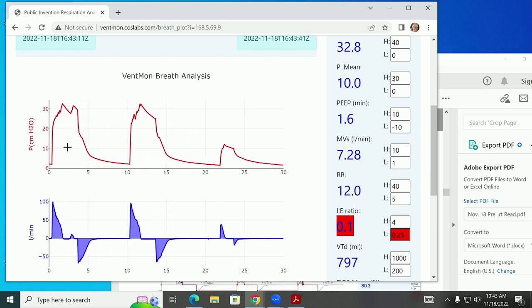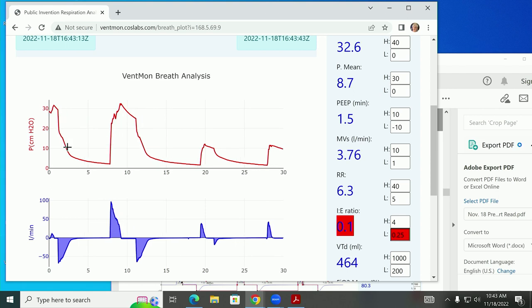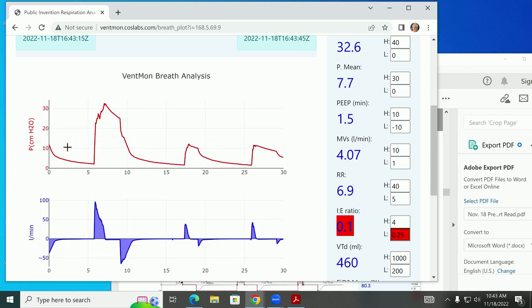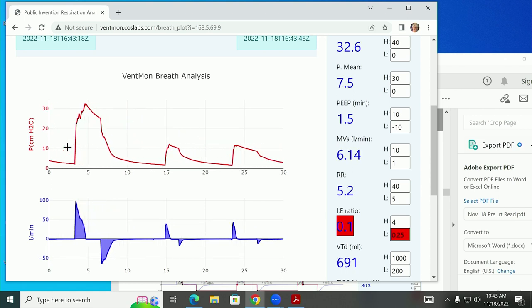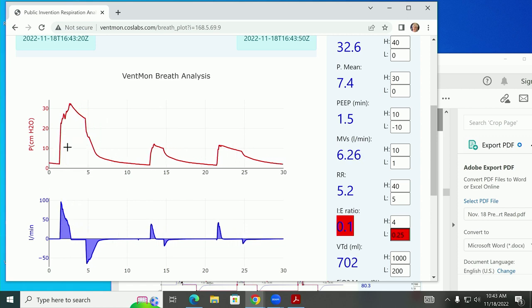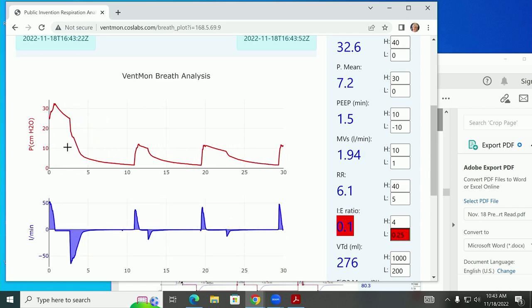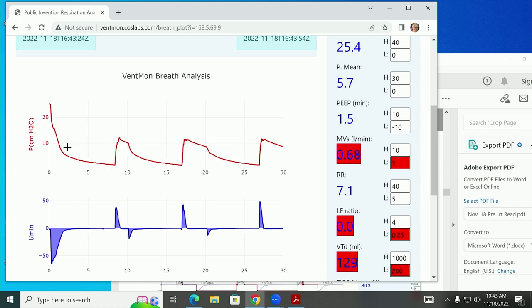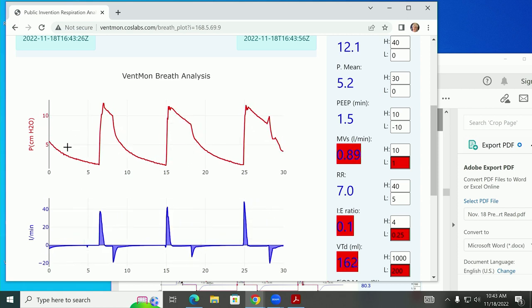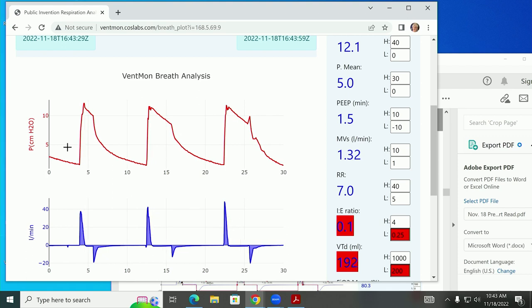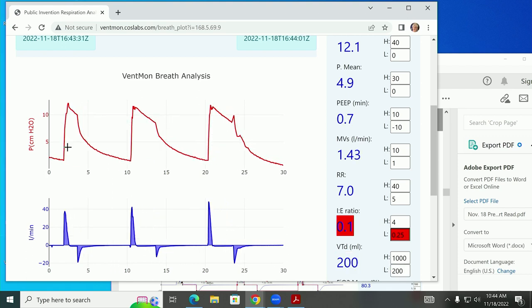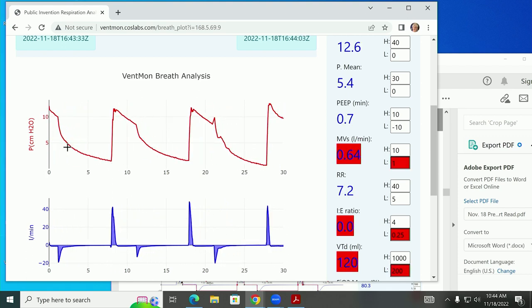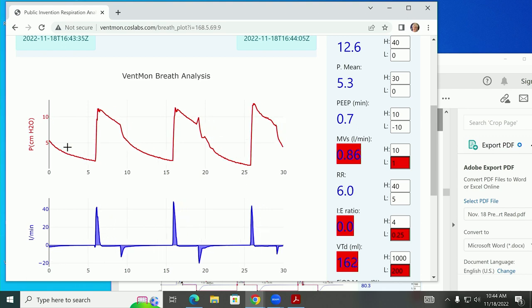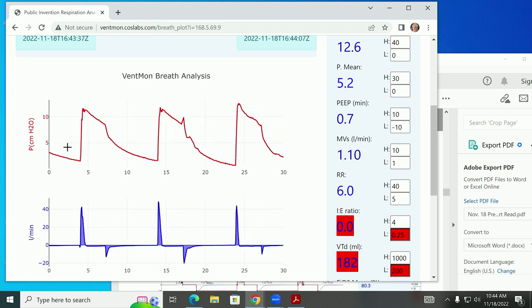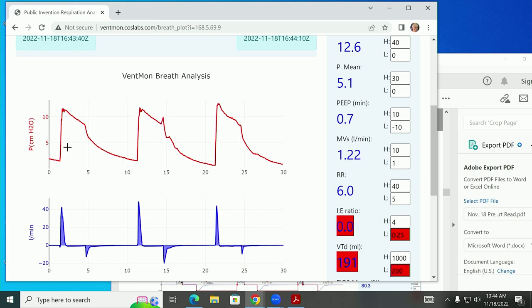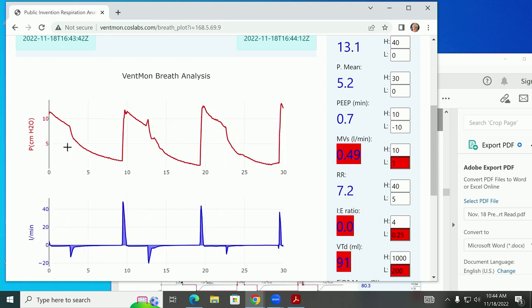Let me interrupt. I've lowered the pressure to 10 centimeters of water, which would be a little light. Can I have a volunteer put your hand on the test lung and hold it down a little bit, and you'll see how the PID loop adjusts to it. Go ahead, put a little pressure on it, and we'll see it in the waveform. It lags by about 5 seconds because of the internet and all that. We should be able to see a change. Yeah, less volume has gone through because we're aiming for that pressure, right?